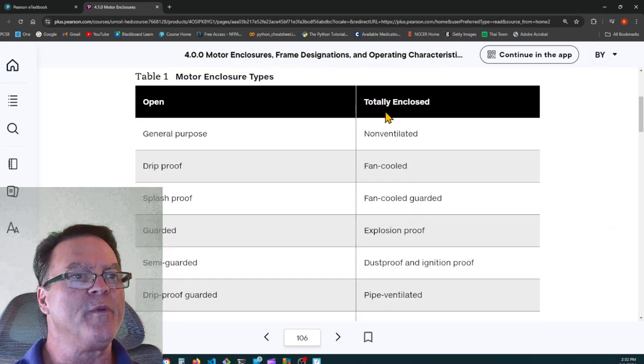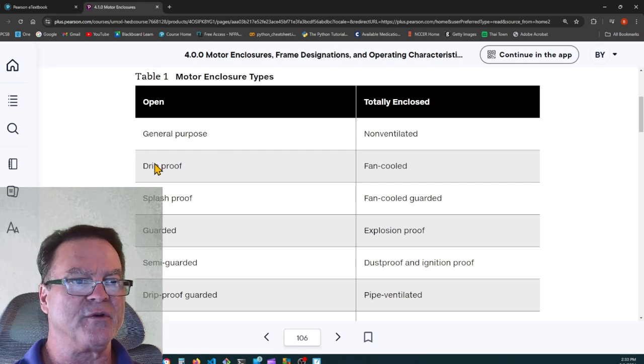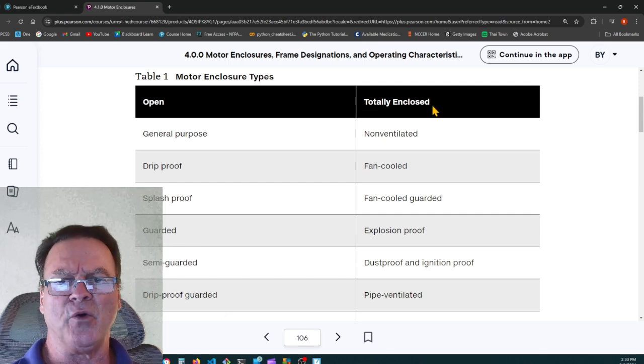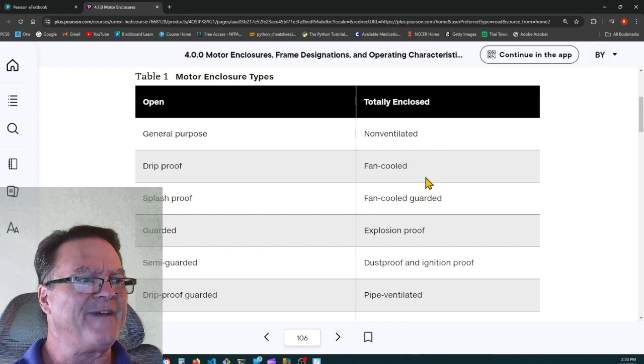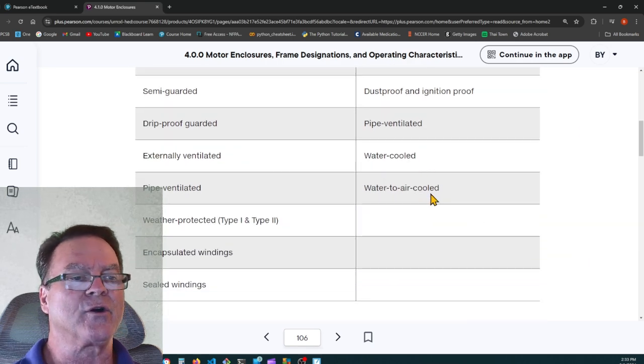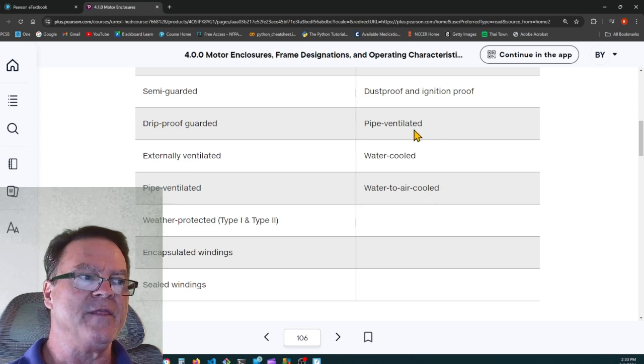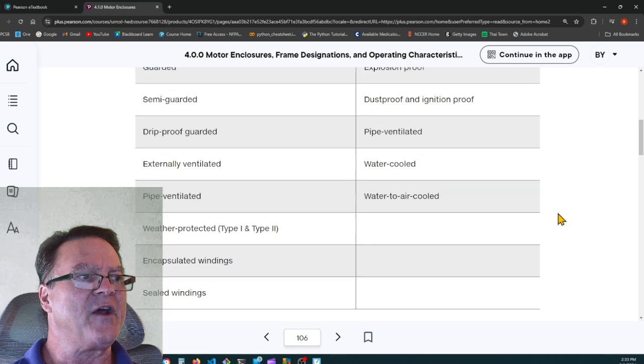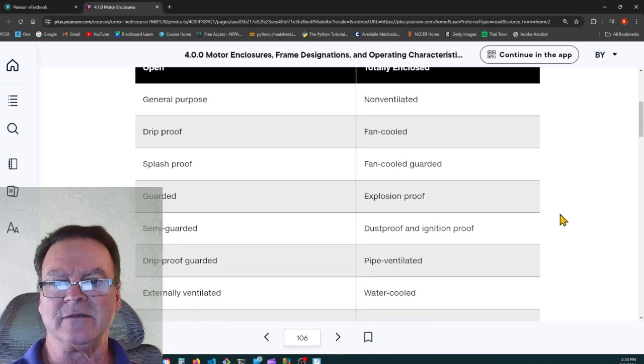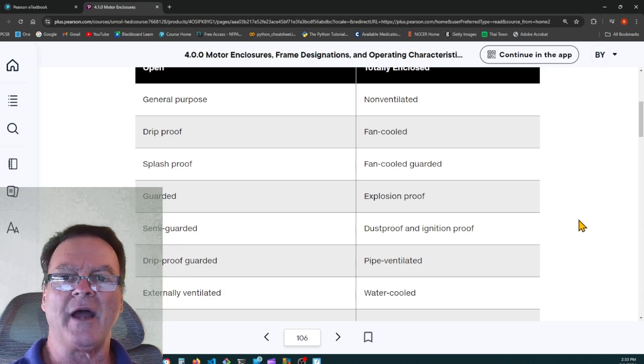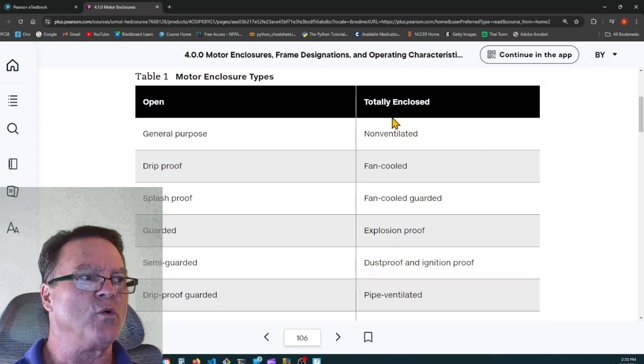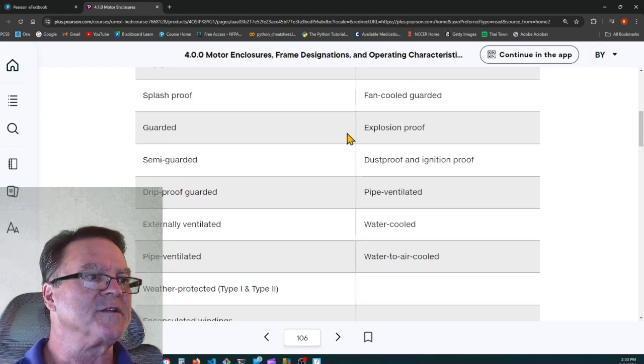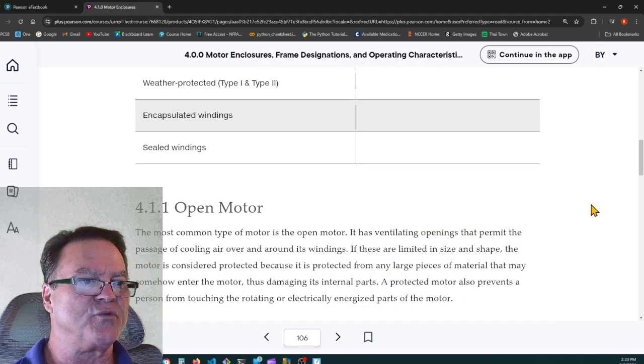So here are some open and totally enclosed motors. A general purpose motor, drip proof, splash proof, guarded, semi-guarded, drip proof, guarded. The totally enclosed enclosures are non-ventilated, fan-cooled, guarded, explosion proof, dust proof and ignition proof, pipe ventilated, water cooled, water to air cooled. They're completely encased so that if they are in an explosive environment, they're hermetically sealed and the sparks contained in the motor will not ignite the environment outside of the enclosure. They're totally enclosed, especially the ones that say explosion proof, dust proof, and ignition proof.